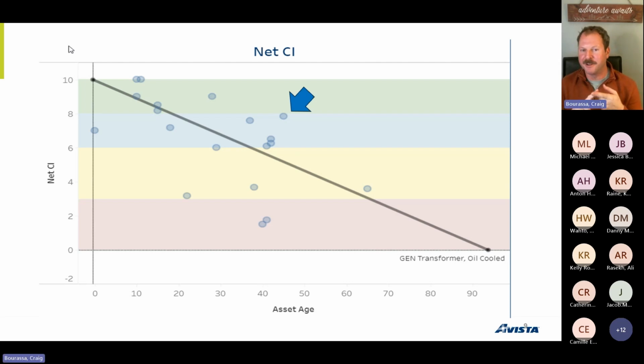How has it been operating? Do you have a bunch of outage time with it? That gives you a score. Do you have a lot of maintenance associated with this? Do you have a lot of physical inspection? Do you have oil leaks currently? Do you have any signs that you have a failure coming on this transformer? So that gives you a rating system.